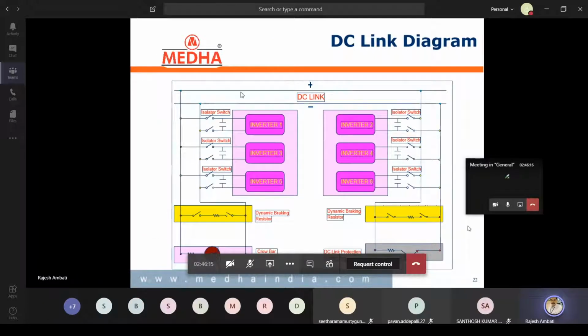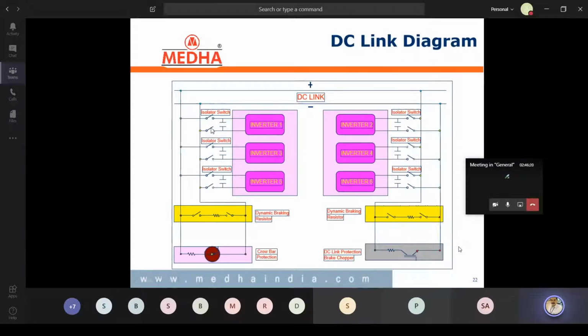This is the DC-link diagram. Overall it is the DC-link supply, positive, negative. Here 3 DC-link contactors, both positive and negative contacts. Here 3 DC-link contactors, and on this side 3 DC-link contactors. Each and every contactor is connected across the DC-link supply. So during normal operation, if we keep the isolation switch in run position, all the 6 DC-link contactors will get closed if everything is okay.